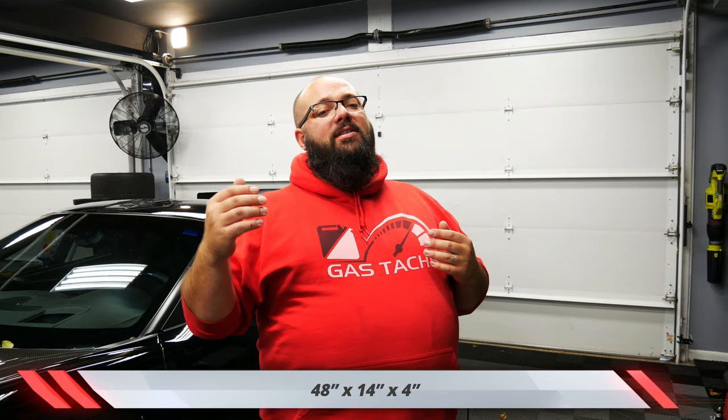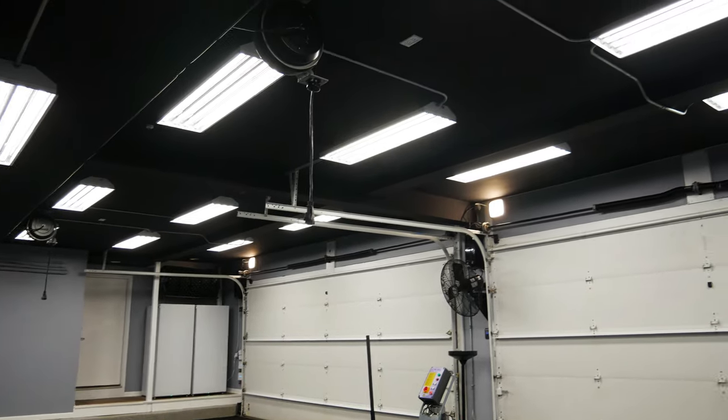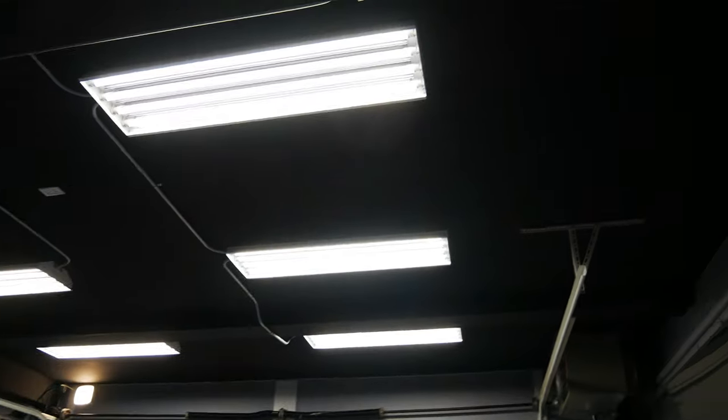So let's jump into some specs. These are 48 inches long by 14 inches wide and 4 inches deep. I have 16 fixtures in here and these are four-bulb fixtures. Each bulb is a one-sided LED bulb and it is frosted. These bulbs are also 5000 Kelvin bulbs. I have all my lights surface mounted with exposed conduit because I think that looks cool, but you can also chain mount these lights. Each fixture draws 0.74 amps, so you should be good with a typical house breaker.